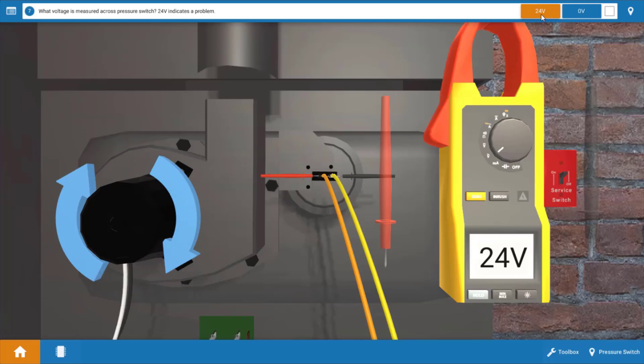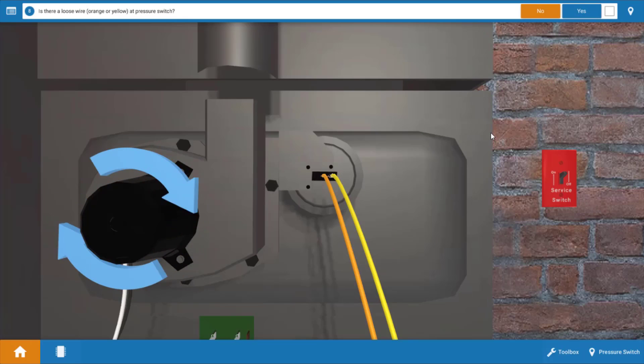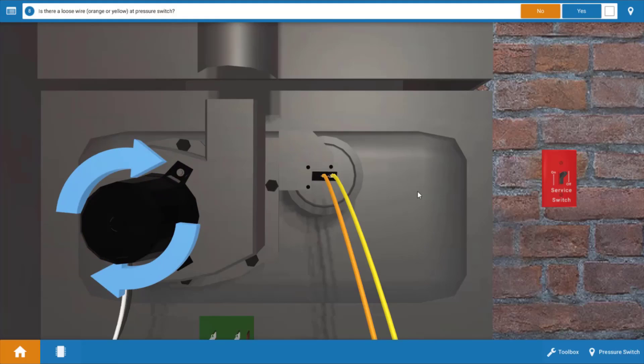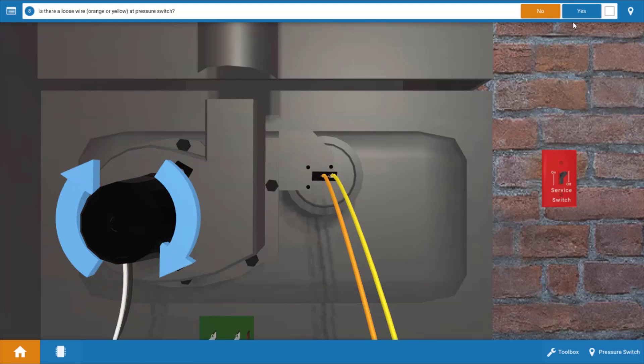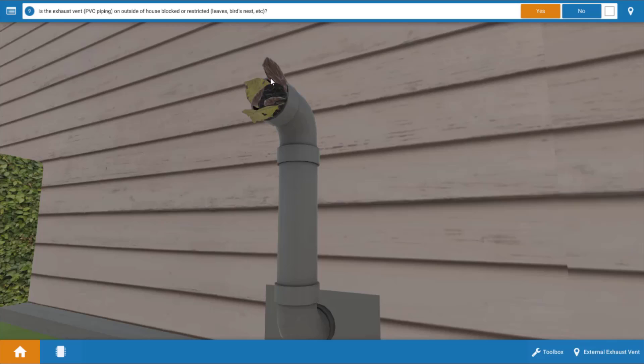So we're going to click 24 volts here at the top and our next step is we're going to check for some loose connections and we don't have any loose connections there. Our next step would be to inspect the vent and when we go outside we can see that there in fact is an obstruction in the vent. It's blocked by leaves.